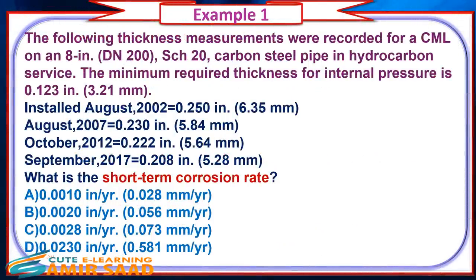Example 1: The following thickness measurements were recorded for a CML on an 8-inch Schedule 20 carbon steel pipe in hydrocarbon service. The minimum required thickness for internal pressure is 0.123 inch. Installed August 2002: 0.250 inch. August 2007: 0.230 inch. October 2012: 0.222 inch. September 2017: 0.208 inch. What is the short-term corrosion rate?